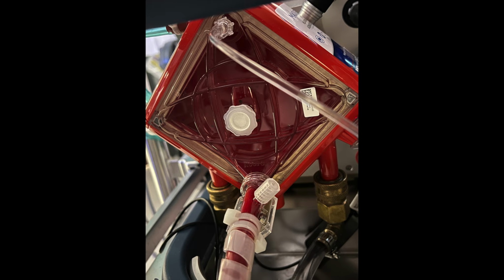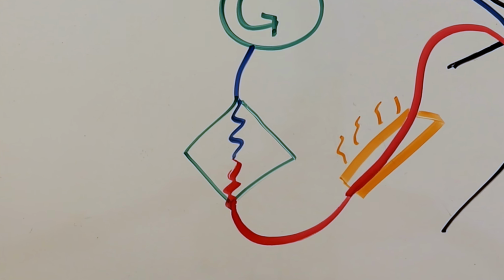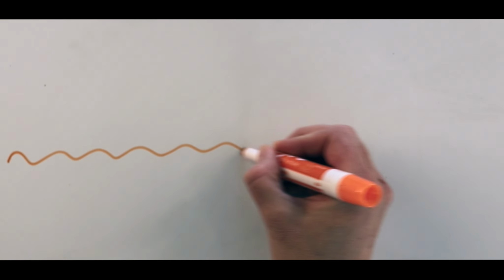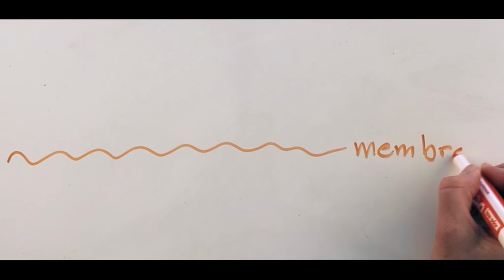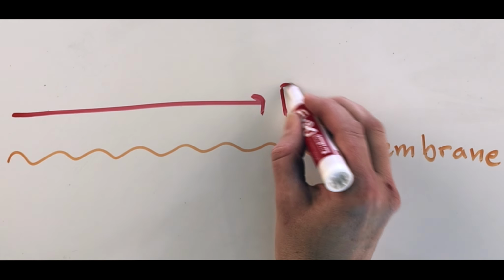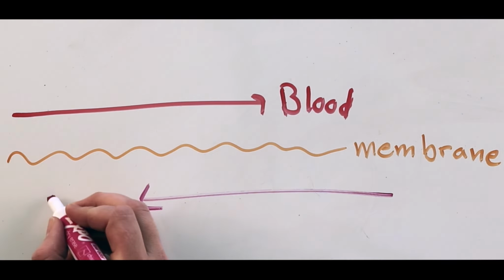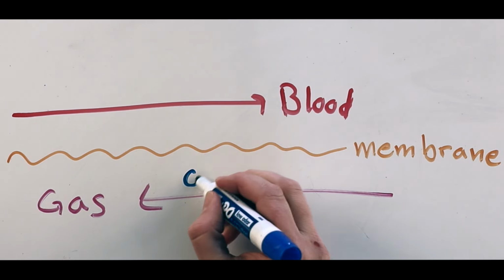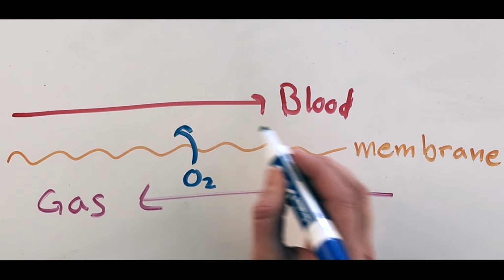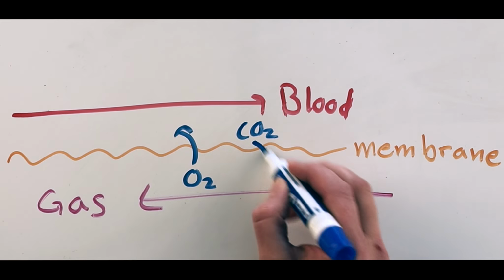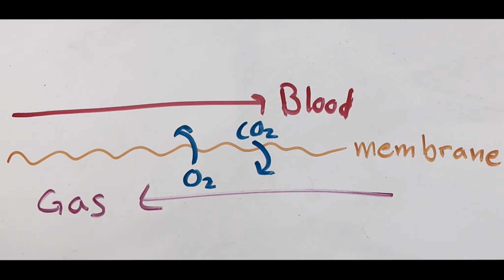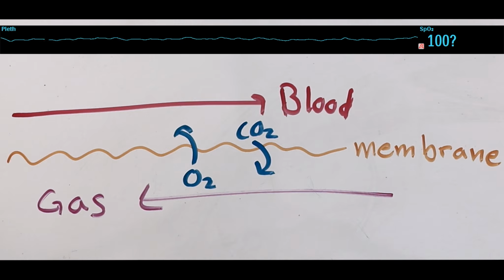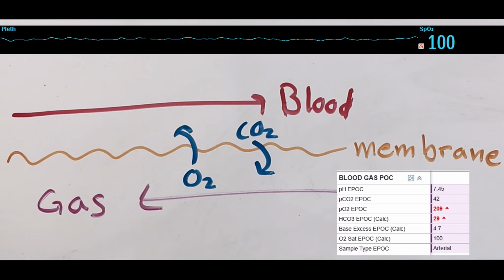Now let's talk about the oxygenator, which not only oxygenates the blood, but removes carbon dioxide, CO2, just like our lungs do. Very simply, the oxygenator has a membrane with the patient's blood on one side and the sweep gas on the other. The sweep gas has a higher concentration of oxygen than the blood, so oxygen diffuses into the blood across the membrane. The sweep gas does not contain CO2 unless it's added in, so CO2 diffuses from the blood to the gas. We need to set the sweep gas to maintain the patient's oxygen saturation within goal and the CO2 at a level that gives us a reasonable pH.